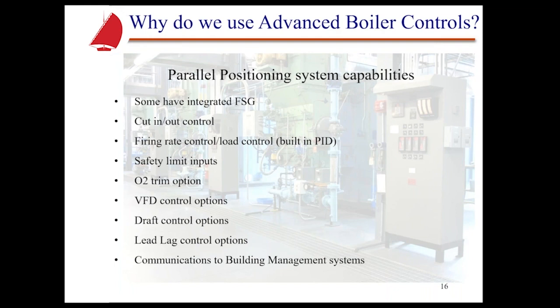Also, safety limit inputs. If you look at many of these systems, the safety limit inputs are built in also. O2 trim option, and we'll talk about this more later, but by being able to add O2 trim, we're going to add a feedback that can make that difference when the ambient conditions change in the combustion air. Variable speed drive control options. Many of the parallel positioning systems offer at least one.